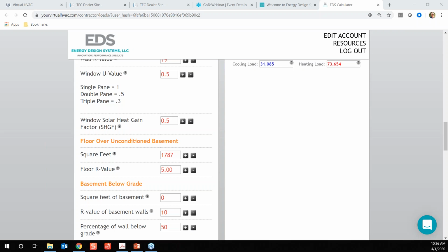So normally with 2 system houses, and I've done a few of them with this tool because I'm, once again, lazy and I don't want to actually do a full load calc with Wrightsoft, which is a fantastic software tool, by the way. But I'm lazy, so I will use this tool. So let's say I'm doing the upstairs system, which I did for one of my coworkers a couple months ago. I used this tool. I did the whole load calc and told him, hey, your whole house needs 6 tons of cooling. You have 2 4-ton systems. In general, your whole house is oversized.